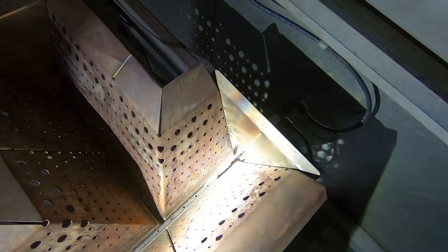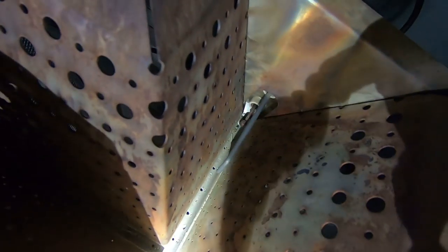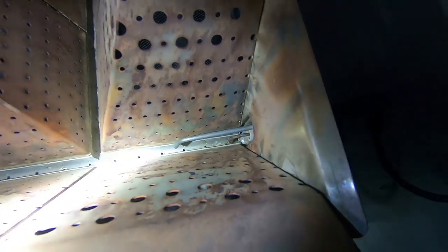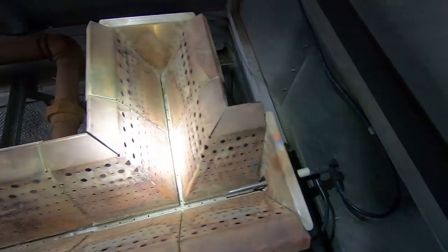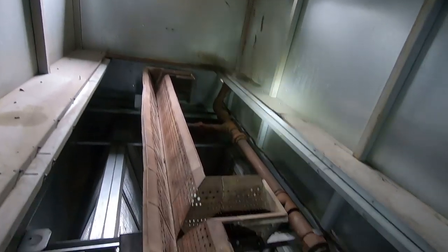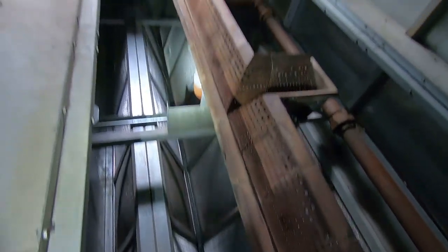Alright, down here on the end is the flame sensor and it was dirty. Plus if you look down in the very bottom there, you can see little bugs and stuff in there that are blocking some of the holes. That can cause you some issues with it not lighting. Sometimes you can run a drill bit through these things, blow them out with nitrogen. But you're actually in here where the blowers are at, so you've got to actually climb inside here. Another big reason why you want to lock this puppy out so you don't get crispy crittered or sucked into a blower.